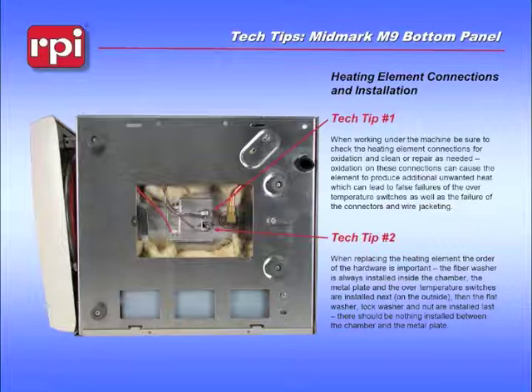This is where the heating element comes through, and we have connections to our circuit board for 120 volts AC to come on to the heating element. These are quick connect fittings that over time can oxidize. You need to pay attention to them. Also, there is a series of seals around the heating elements to keep the steam in that you need to pay attention to. If you ever see buildup of any sort of calcium or lime here, or if you actually see water anywhere near this, you need to make sure that those seals have not failed.